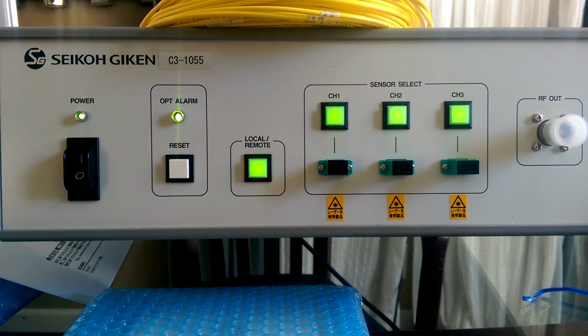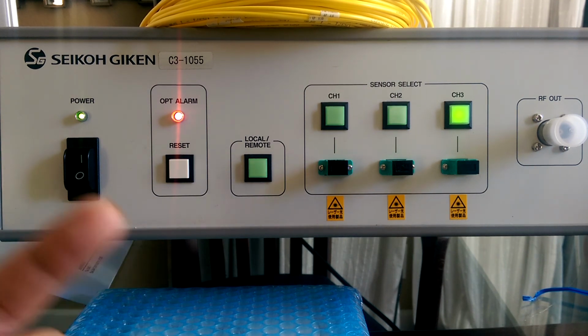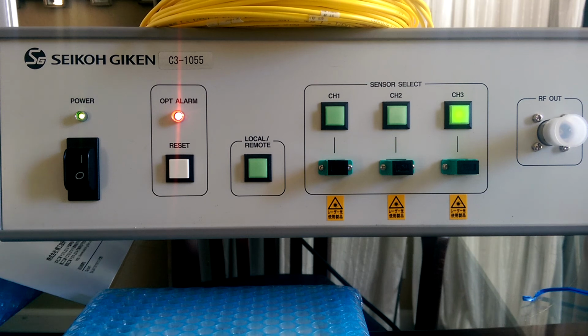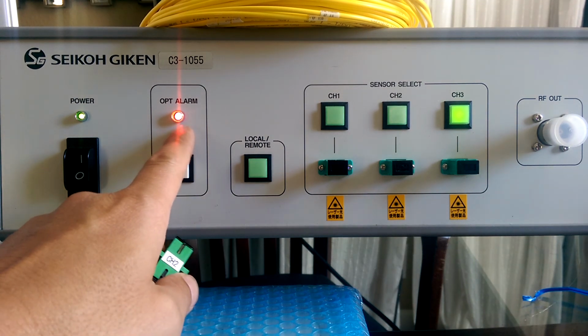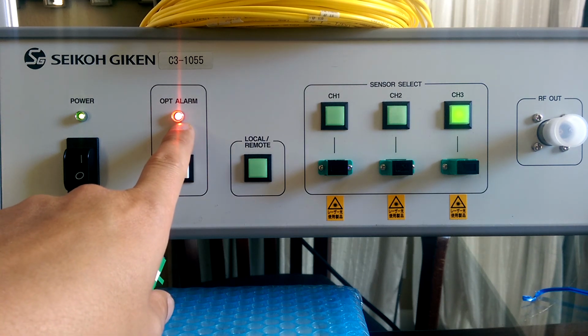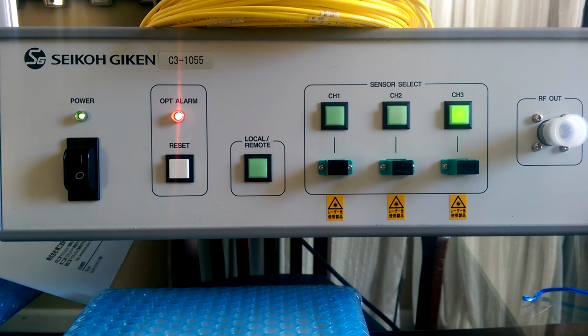When you turn the power button on, everything will illuminate green at first. It does a self-diagnostic on internal components and checks the insertion loss of your fiber lines. If the insertion loss is too great on any of the fibers, it triggers the optical alarm and that light illuminates red, which shuts down the laser diodes so you can't make any measurements.